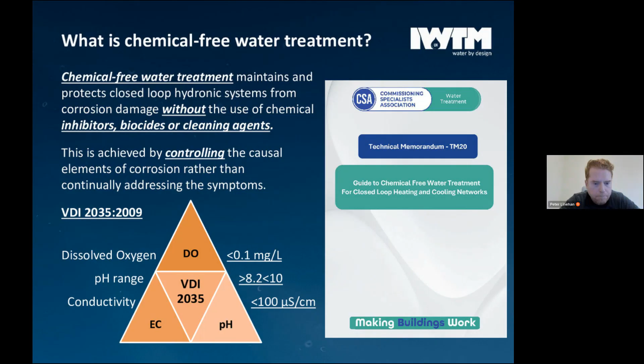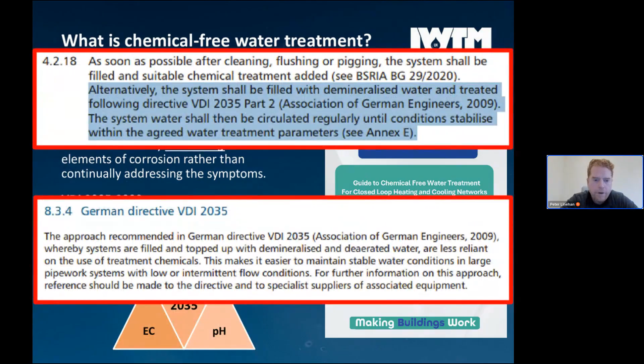Oh, and this is not the first time that VDI 2035 has been mentioned. Back in 2001 or maybe 2000, the CIBSE CP1 guide mentioned it as a viable alternative to chemical dosing. You can fill with demineralized water and treat it as followed by VDI 2035. It's also mentioned in CIBSE's Heat Network Design Guide as the VDI being better for large pipework systems with low and intermittent flow situations. So it's not the first time that VDI has been brought up, but now in 2026, this TM20 guide is based on VDI 2035.